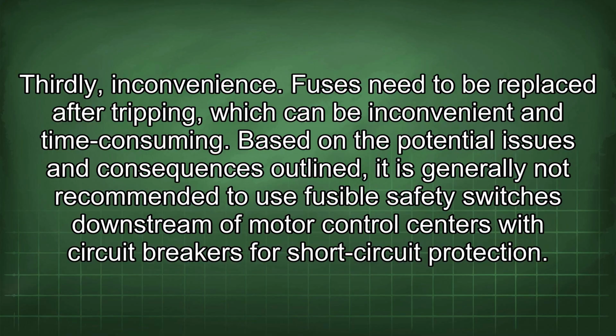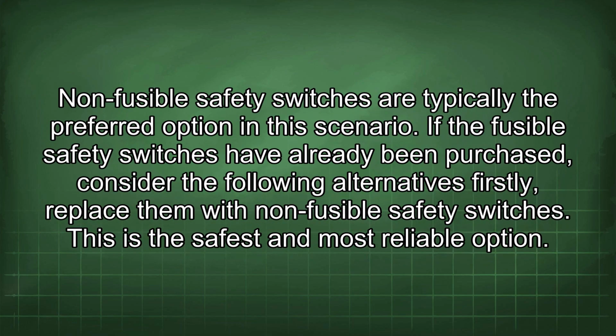Based on the potential issues and consequences outlined, it is generally not recommended to use fusible safety switches downstream of motor control centers with circuit breakers for short circuit protection. Non-fusible safety switches are typically the preferred option in this scenario. If the fusible safety switches have already been purchased, consider the following alternatives. Firstly, replace them with non-fusible safety switches. This is the safest and most reliable option.